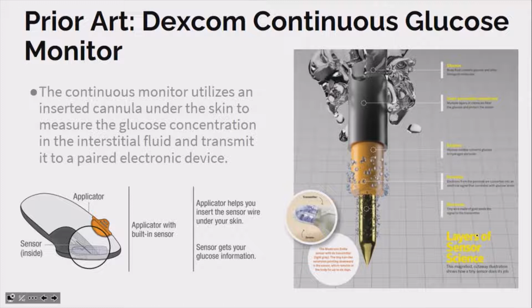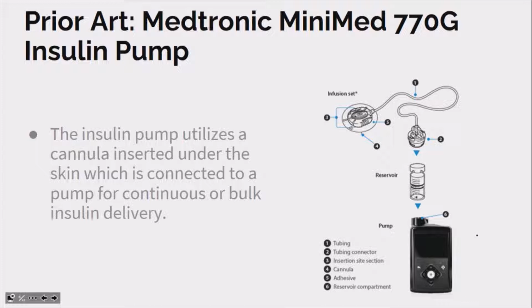Second device that we referenced was a Medtronic insulin pump. So to get an idea of how current devices are used, the infusion set that goes into the skin has a small cannula that needs to be applied with an applicator that uses a small needle to inject the cannula under the skin. And it connects to the insulin pump, which has a reservoir where the insulin is stored, and then based on whatever values the doctor dictates for the blood glucose value, the insulin is injected for a certain volume by a piston, which injects that into the tubing and into the applicator.